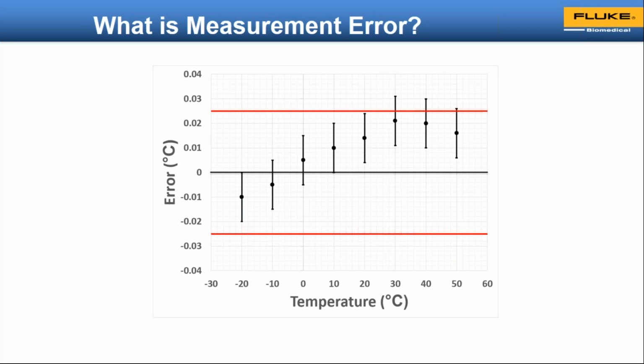And it's a stack up of a series of different factors when you look at it. So we can see that the red lines are our upper and lower testing limits, our pass-fail criteria. And we can see that the data at the top right of the screen, those three measurement points, we might consider pretty close to the limit. And if we're only going to look at this medical device for testing once or twice in a year, there could be drift of that measured value outside its acceptable limits. And we might or might not make a decision to do something about how close those are to the limit.